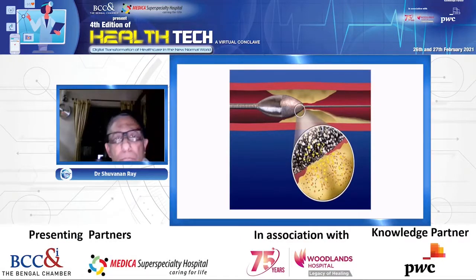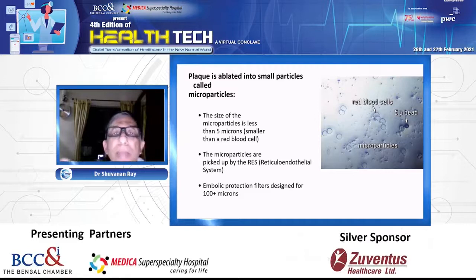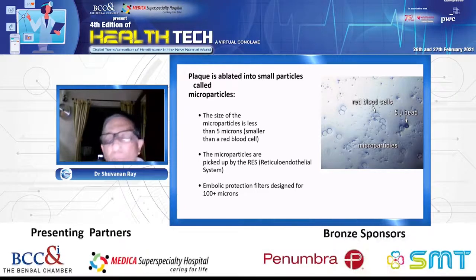It is done by this bullet, shown here more clearly. You can see it has two parts: the forward part and the backward part. The forward part is studded with diamond crystals, which act as a cutting edge. When this bullet rotates at very high speed, like 150,000 to 2 lakh rotations per minute, it crushes the calcium layers of the artery and pulverizes it. These pulverized particles, less than 5 microns in size, are taken up by the reticuloendothelial cells of the system and washed away from the arteries.